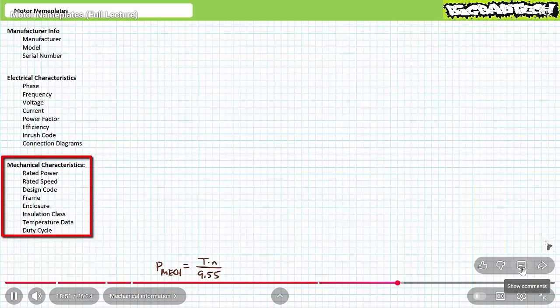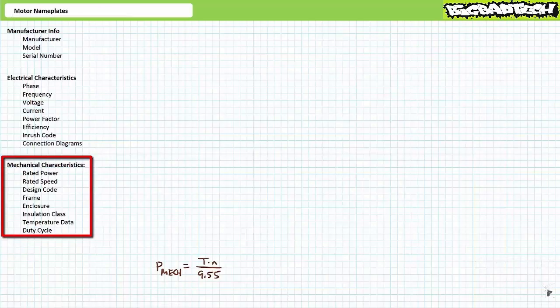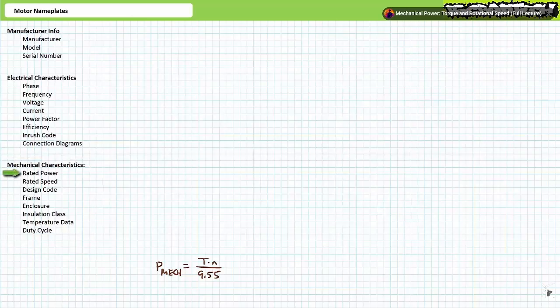specify mechanical power, rated speed, design, frame, enclosure, insulation class, temperature data, and duty cycle. Mechanical power. The power entry in a motor nameplate is the output mechanical power in units of horsepower or watts, where 1 horsepower is 746 watts.